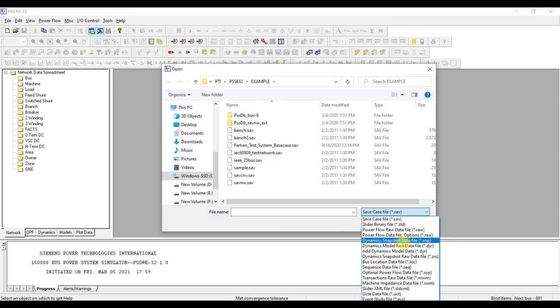Similarly, if we want to transfer data into another software and import PSSE data elsewhere, we convert the file into a RAW file. If we have a power system case available in another software like DIgSILENT or ETAP, we can import it into PSSE using the RAW file, because all these softwares have the capability to export their power system model into RAW format.